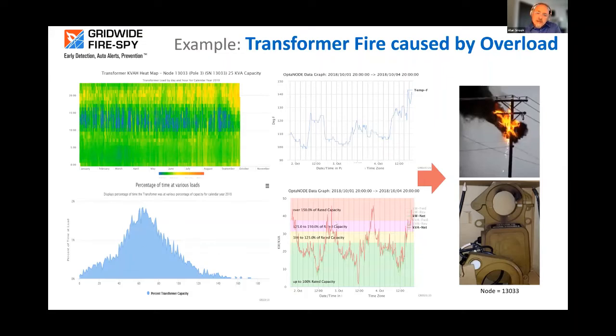Each of these four panels of information are the kinds of intra-grid analytics data we're pulling from the grid that let us understand and report to utility operators assets showing signs that could lead to end of life, premature failure, or conditions resulting in this fire scenario. All four panels were on the exact transformer that this advanced transformer infrastructure sensor was on when it went up in flames.